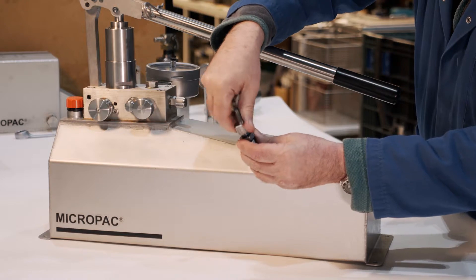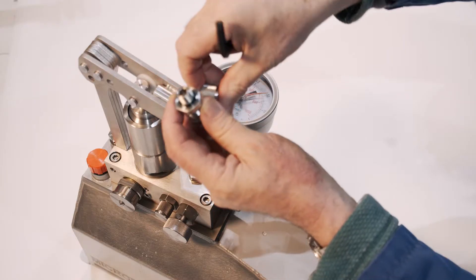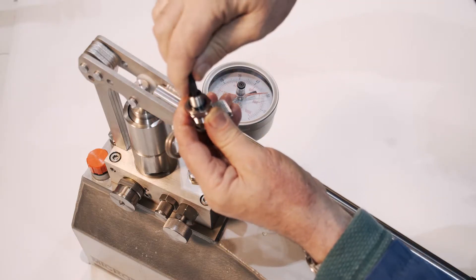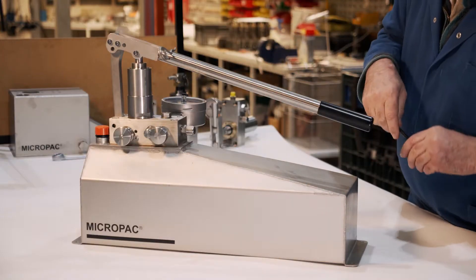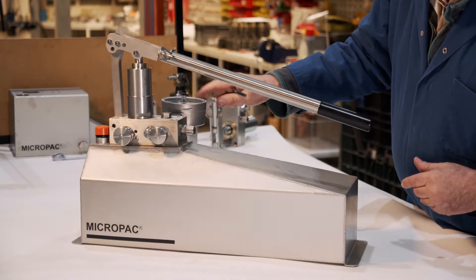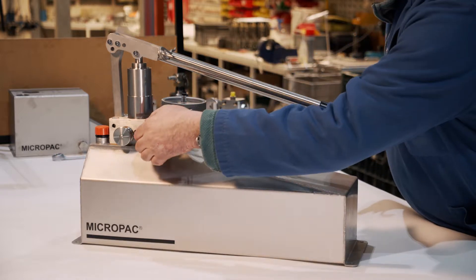Relief valves invariably have an adjusting screw. In this case an Allen key fits into it. I'm going to adjust the setting on this pump here. I want to get up to 50 bar on the pressure gauge.